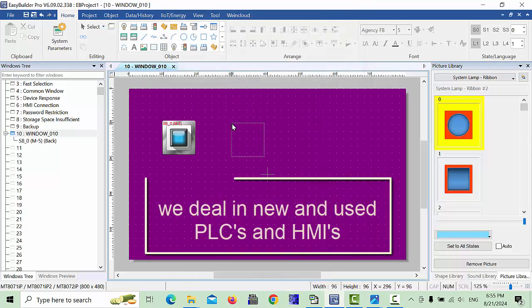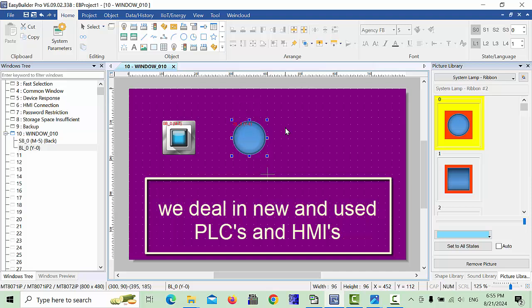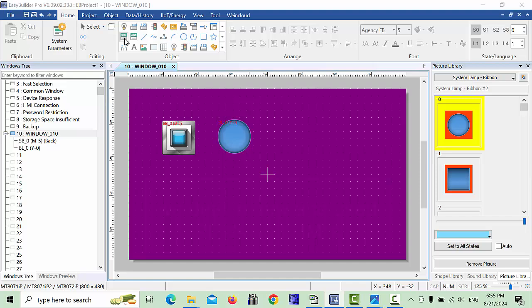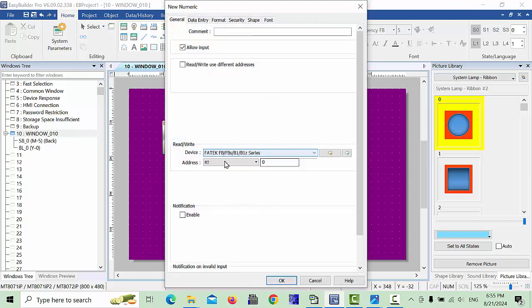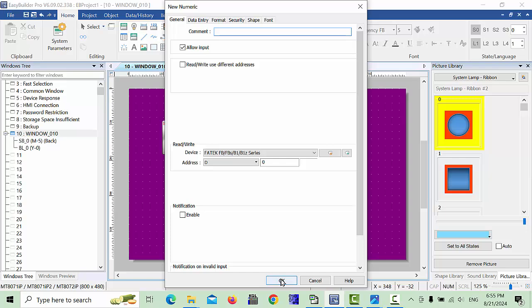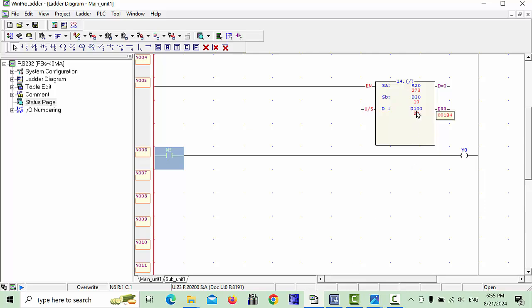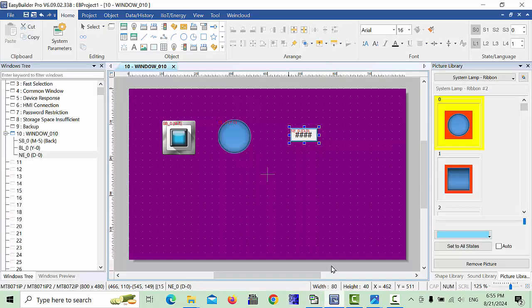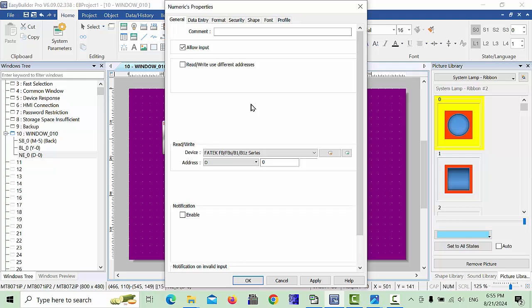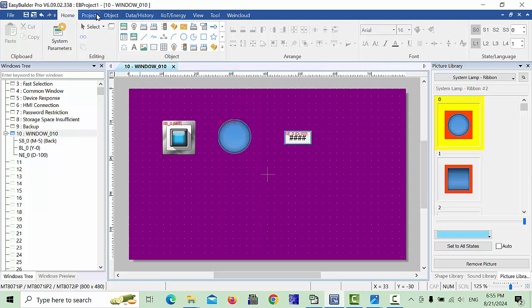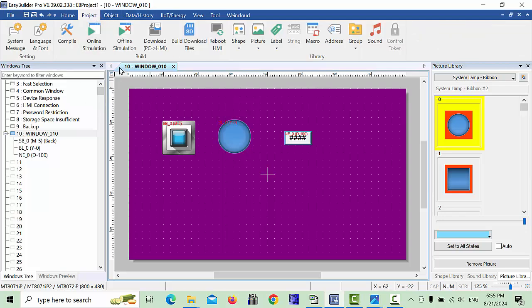You can put any lamp. For example, this address you will put Y0. Click OK and you can place it anywhere. If you want to see the numeric data, go to numeric entry and here you have to give the address of your temperature or whatever you're using. Cross check this one - D100. So you have to choose the address D100, and your temperature will be shown on the HMI. Now I will complete the program and download to the HMI.